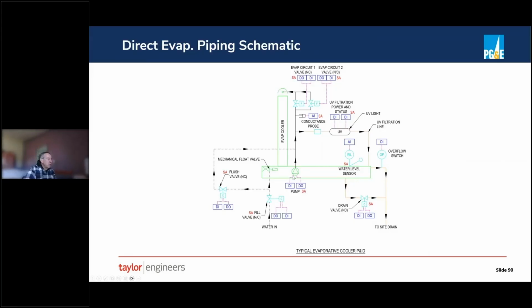And typically in the winter, when you're not using the evap, we'll shut off the flow so this can't be filled up, and then we'll just drain it out so it's dry. So a lot of the year, this sump is dry. When your air handler deck PID loop starts to call for cooling, then we'll fill up the sump, turn on the pump, open the valve, and get the flow.